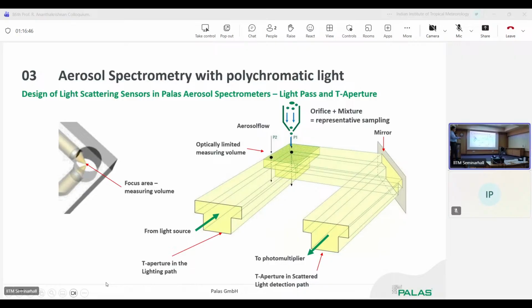Here in that area, particles are coming from the top, and they fly through the optics or through the sensor area here. And as you can see here on P1 and P2, particles can fly in the inner area or fly in the outer area. This particle, for example, flies in the outer area, and this particle flies in the inner area. And we have a T-shaped aperture on the backside, where the light is going out to the photomultiplier. And with those T-shaped apertures, we form this specific measurement area, which looks finally like a 3D T from both sides, either from that side and also from that side. How does it work?